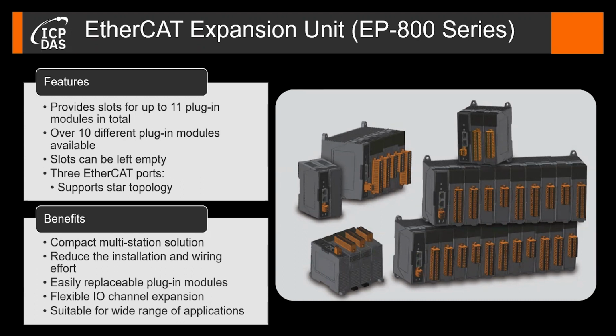The benefit of the EP800 series is that plug-in modules can be quickly and easily inserted and removed from the front of the rack. Plug-in modules are easily replaceable. If one plug-in module fails, it can be replaced while the system is running. So it supports hot plug.